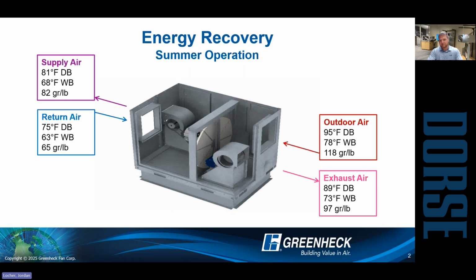Okay, so at the absolute basics, for anybody who has not seen it, hopefully we all know what an ERV looks like. It's pretty basic. On the right-hand side here, you have your hot and humid outside air. It's going to come through the wheel. The wheel is going to exchange heat and moisture across that exchanger, returning that relatively cool and dry air during the summer months. So during the summer, the name of the game is preventing that high temperature, high moisture air from getting into the space.